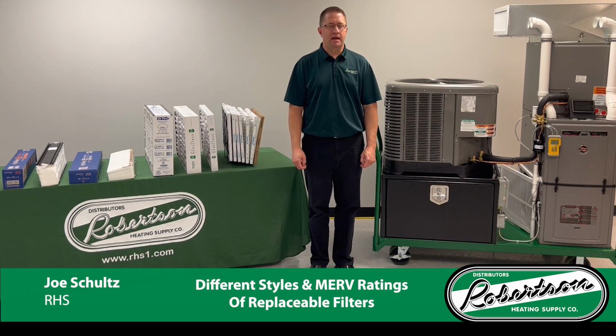MERV ratings of 9 through 12 filter down to particle sizes 1 through 3 microns, which includes everything I mentioned prior, plus lead dust, humidifier dust, and coal dust. Applications include high-end residential, commercial, and hospital labs.